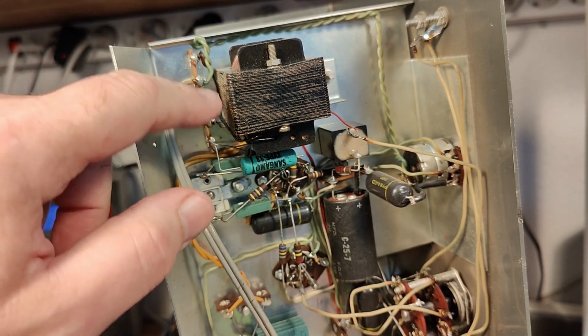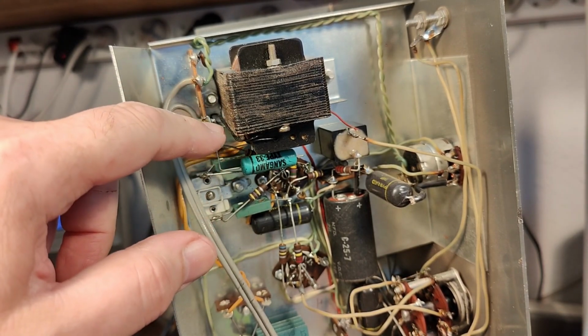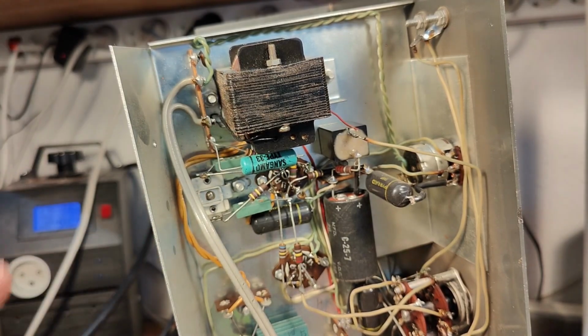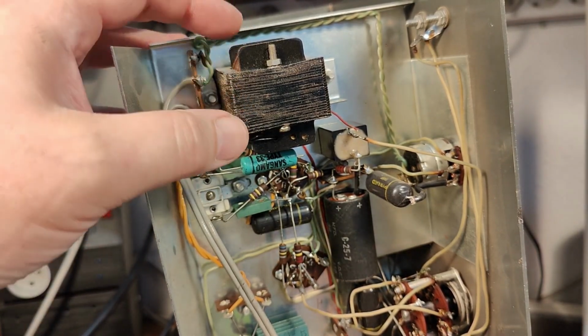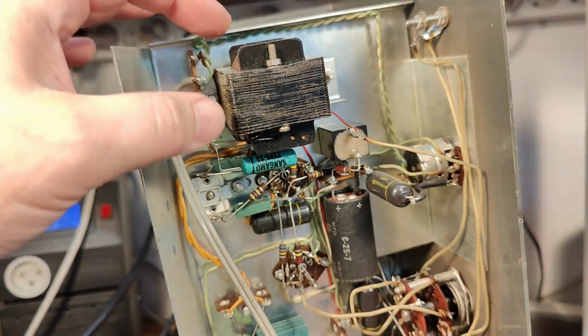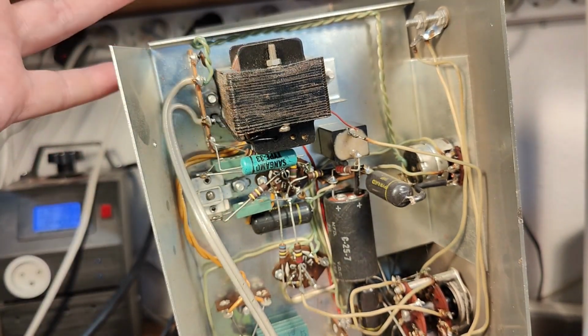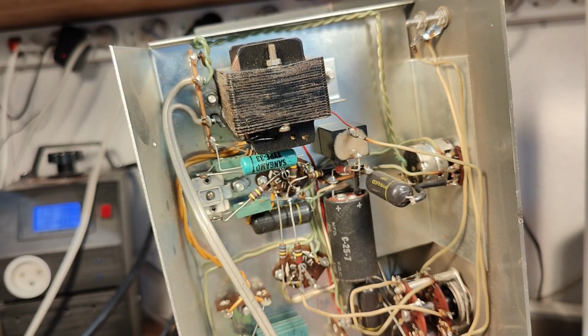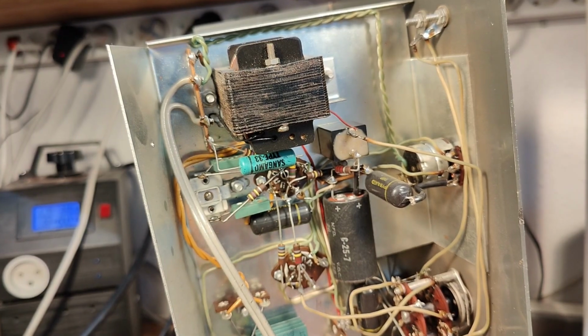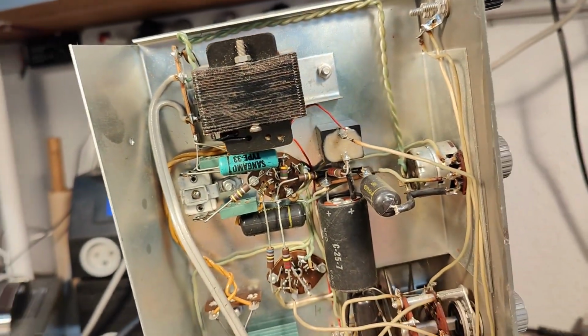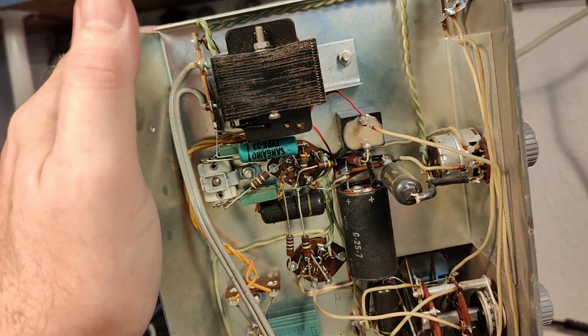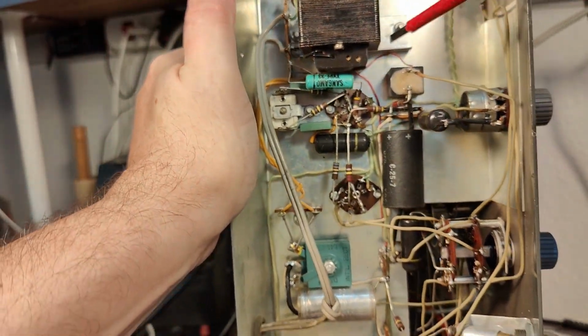And there isn't any other primary winding, so this could be a problem if you import one of these from somewhere else. There is no winding, so it is a big problem with that, right? The secondary side, we got a low voltage and a high voltage. So the high voltage is the red wires.